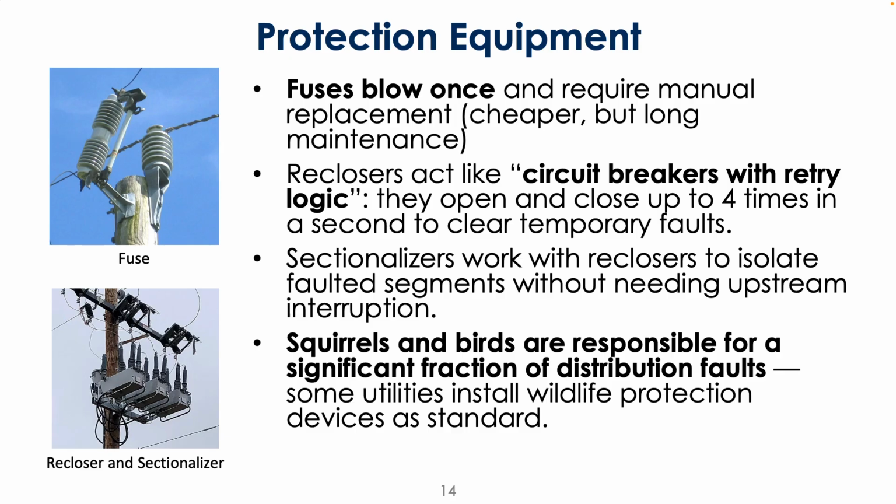With a circuit breaker, there's a physical deformation as the metal heats up if you have too much electricity passing through, and that physical deformation opens the circuit. I don't think they do that here. Yeah, because if it's upstream of the fault, then what would cause it to respond, if it's trying to detect something that's happening downstream and closing it beforehand?